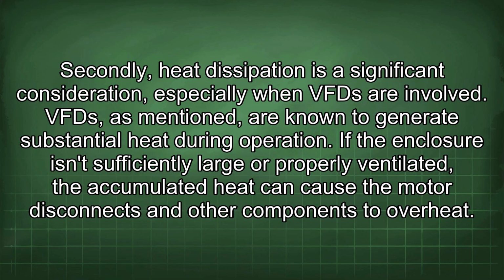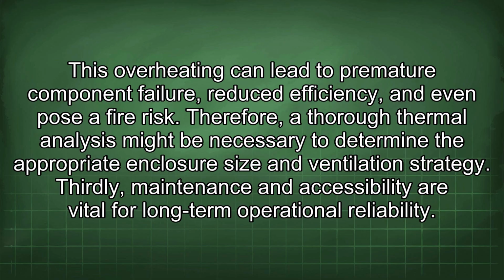Secondly, heat dissipation is a significant consideration, especially when VFDs are involved. VFDs, as mentioned, are known to generate substantial heat during operation. If the enclosure isn't sufficiently large or properly ventilated, the accumulated heat can cause the motor disconnects and other components to overheat. This overheating can lead to premature component failure, reduced efficiency, and even pose a fire risk. Therefore, a thorough thermal analysis might be necessary to determine the appropriate enclosure size and ventilation strategy.